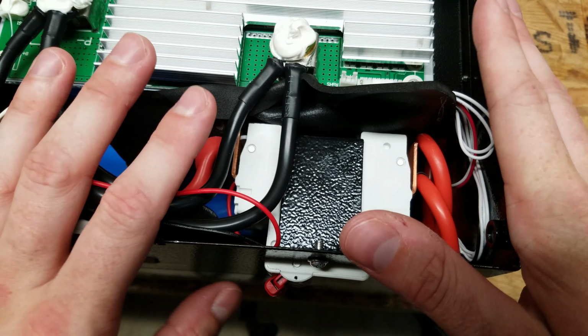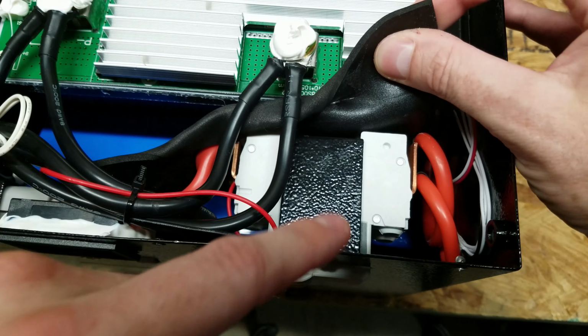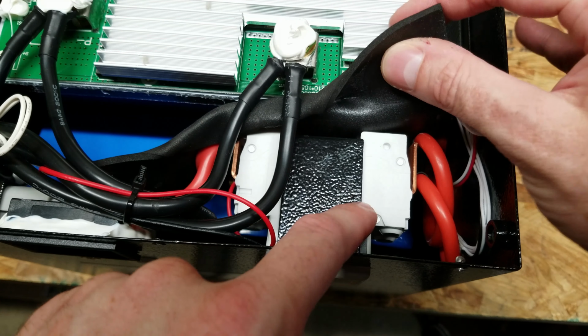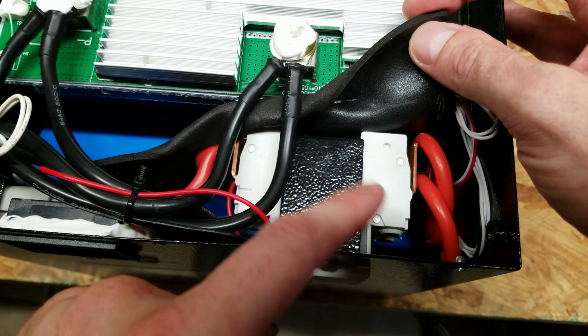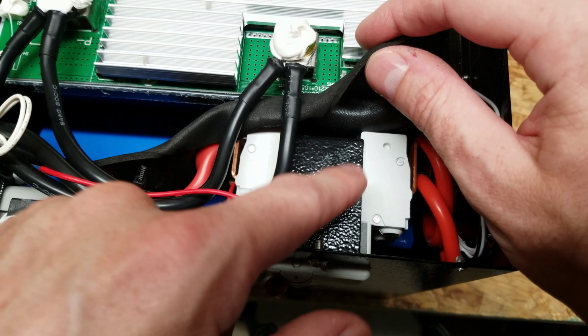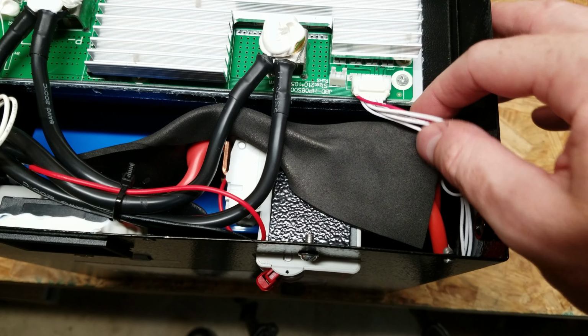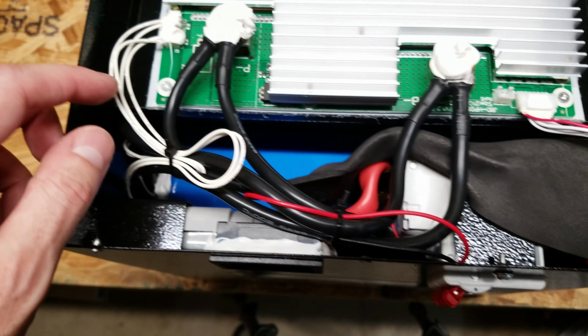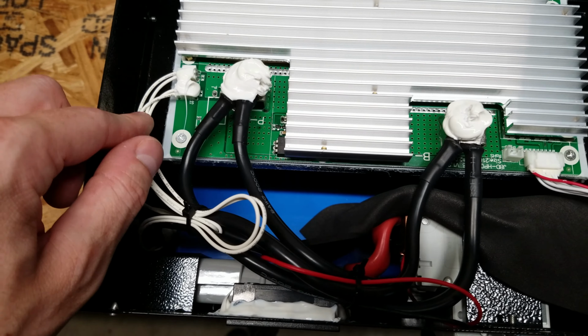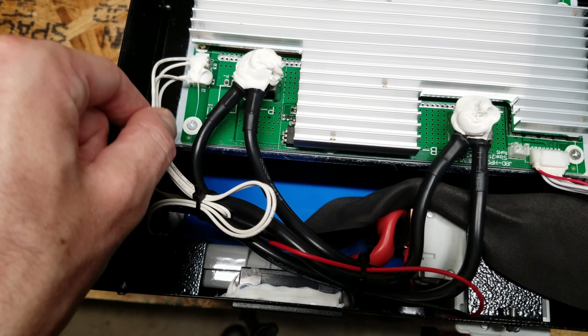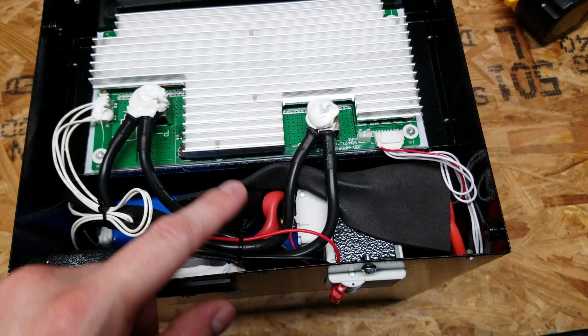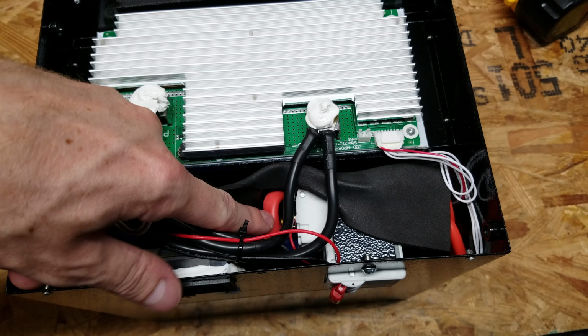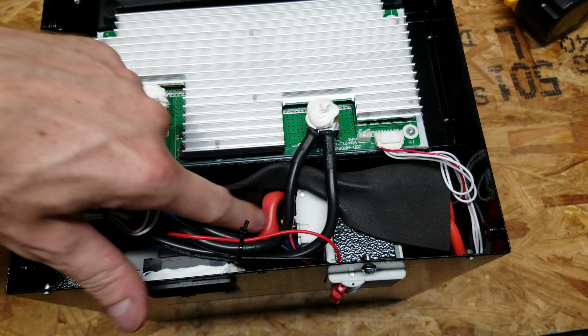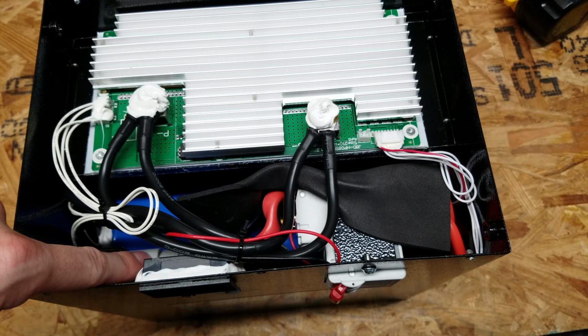I just want to make that clear because I did complain earlier in the video. Whether or not wiring a breaker like this is a good idea is a separate story. I don't personally have a problem with it. Over here on the right we have the BMS wire balancing leads, and the leads on the left are actually temperature sensors, so there are two separate temperature sensors in this battery pack. Coming off the output of this breaker is a single 6-gauge wire which goes from the breaker down to the positive of the Anderson connector.